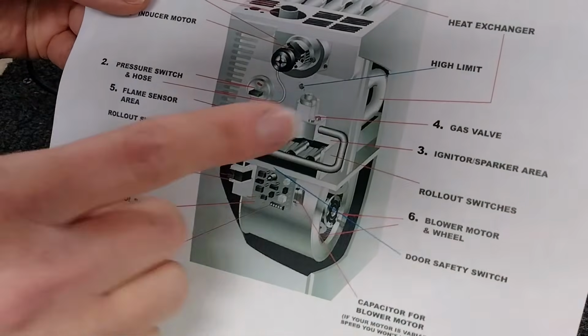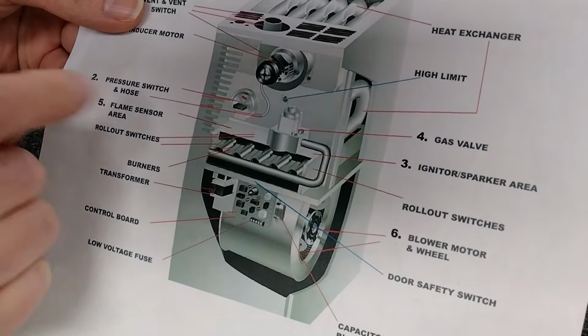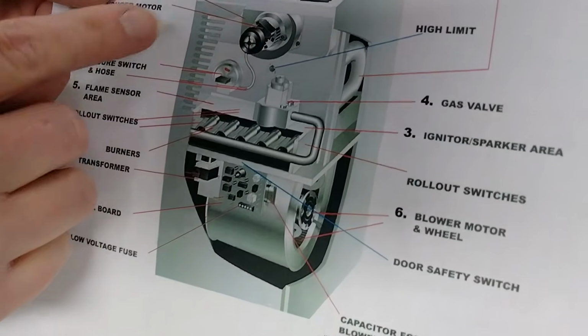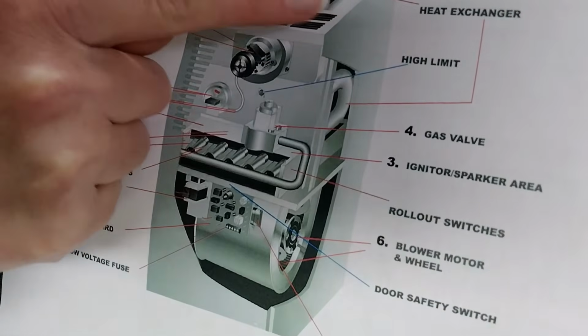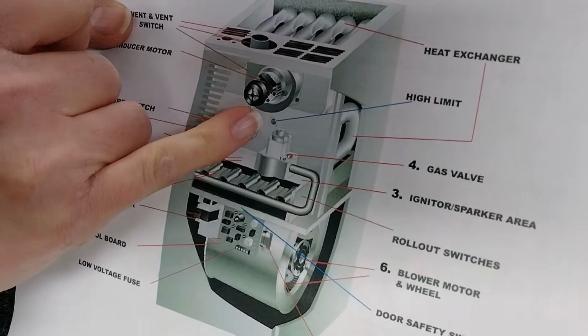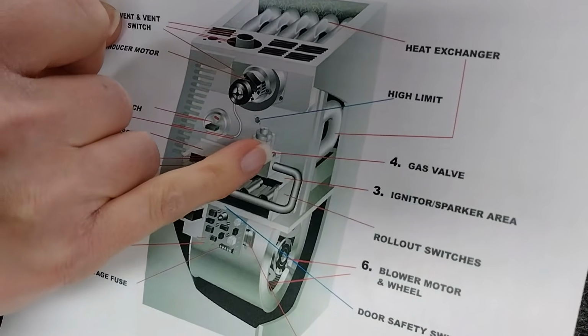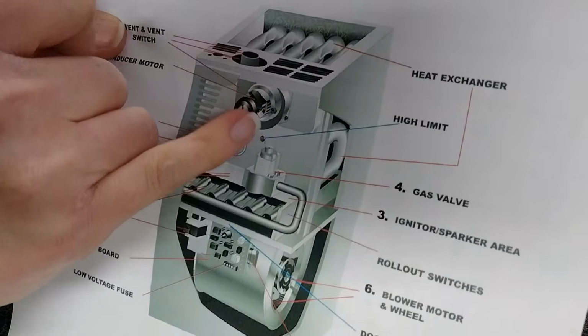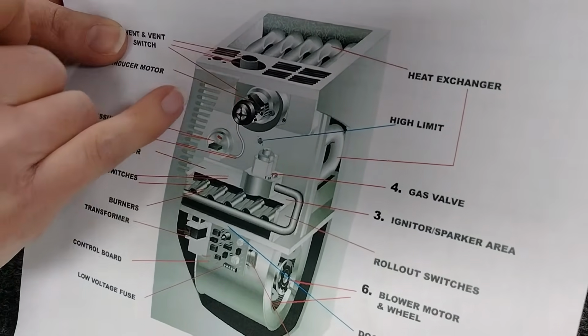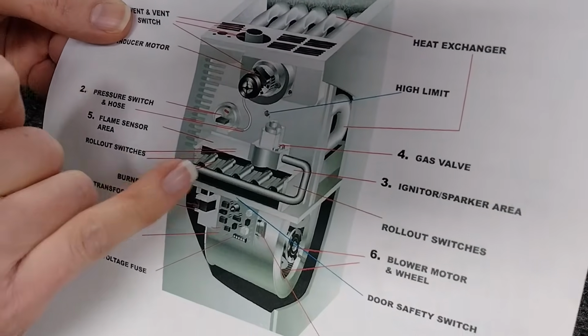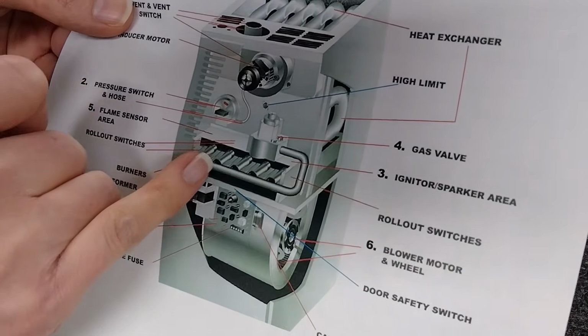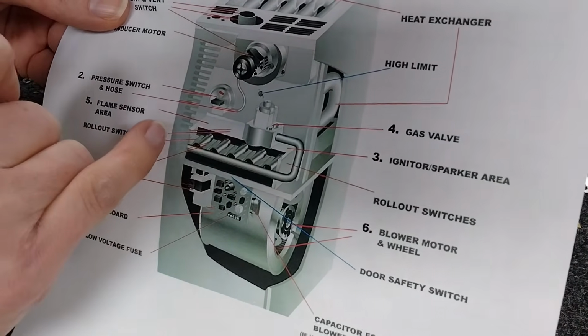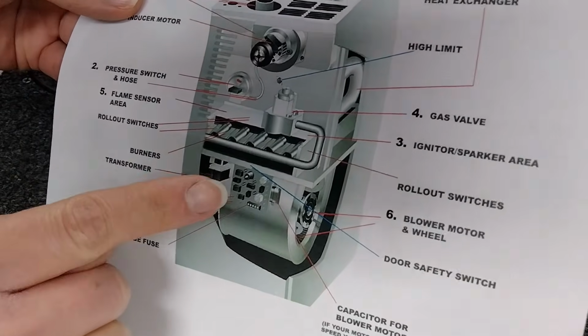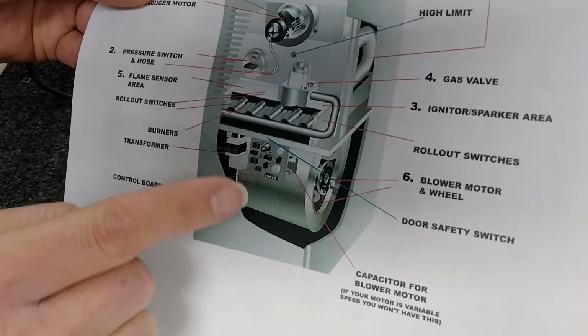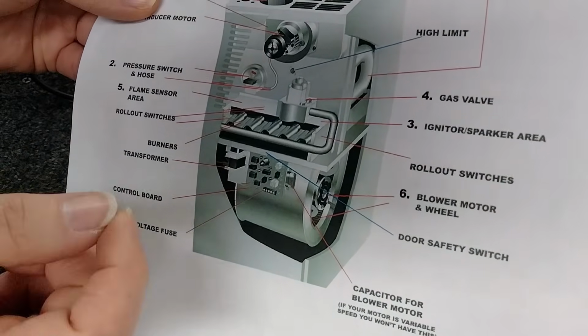And here you can see, pretty typically, your high limit switch, which obviously looks like a normal disc limit there, which high limit switches can look like that. It's usually going to be, and as you can see, your heat exchanger here. Okay. That high limit is going to be along that wall, usually behind your gas valve. This will be your inducer motor, which should be the very first thing that comes on when you start your machine. Your pressure switch, and then your rollout switches should be along your burners. And depending on how many burners you have, will be how many rollout switches you're going to have. And again, you can have disc limits on your blower, whether it's secondary.